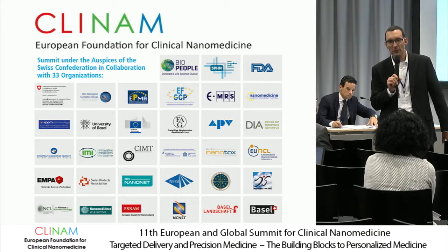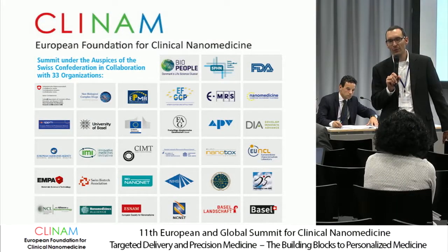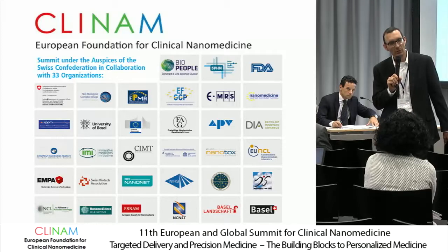So for us, perhaps you remember one of the slides, we evaluated 4 different concentration size standards from different companies, and we were shocked. So 60% difference. On a log scale, it looks great. But if you put it on a linear scale, you see some interesting results. Again, adding concentration is adding another big challenge. I've been in many DIN and ISO committees. Concentration is neglected, and this is really a big thing. There has to be a lot of work to be done.